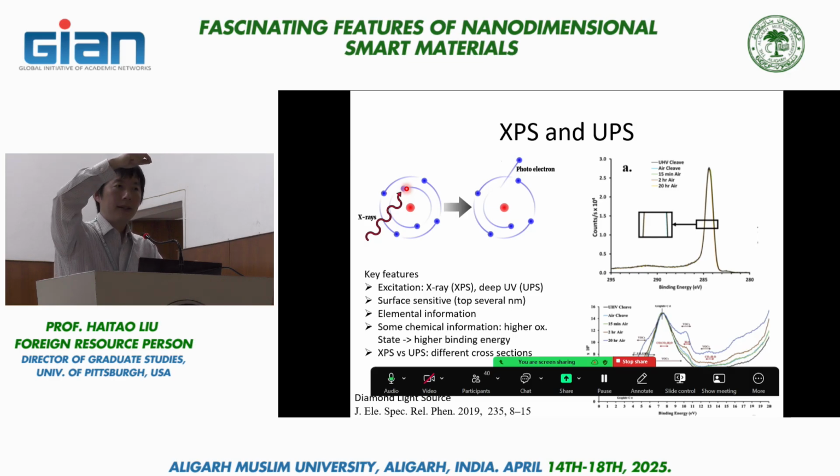Why? Because imagine I have 2 points of photoemission, one near the surface, one deep in the surface. If my detector is closer to the surface, then most of the signal will be the one coming from the surface. Whatever deeper signal will be absorbed, their photoelectron is not going to escape. However, if I increase my detection angle to the normal, I have more likelihood to see the photoemission deeper in the sample. So by changing this angle, I can change the surface sensitivity.